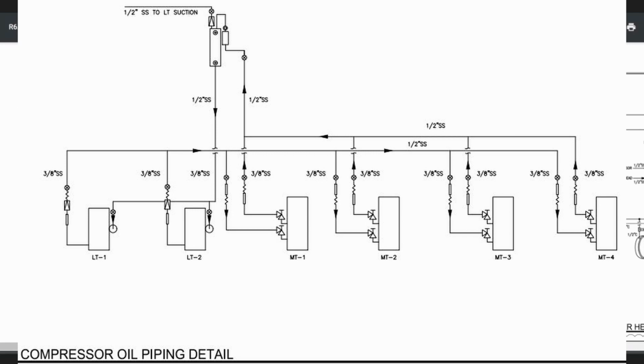Gotcha. So your expected pressures on this system as far as the oil. Now our suction is what, 2 or 3 pounds, right? For the ammonia side, correct? On the low temp, low stage, correct. Okay, so we're running 2 or 3 pounds there. We have that feeding into there, but this line right here is off of the actual oil pump. So it's a Carlyle, you're going to have what, 25, 30 pounds heavier than what that suction is, correct? No, the 5-line compressors run about 50 pounds of net oil pressure. Okay, so we're talking like 52, 53 pounds, right? Right, that pushes it over into the crankcase of the high stage, which are running about 23, 25 pounds.